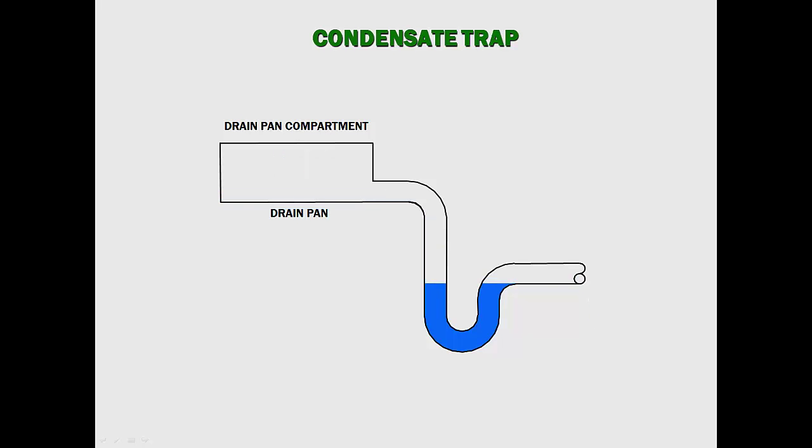When the unit cycles off, the water returns to the trap, and the cycle can be repeated. In theory, the condensate trap appears to be a simple and economical drain seal. In practice, however, it exhibits so many failure modes that it imposes unacceptable damage and contamination on the entire air conditioning system and the building.